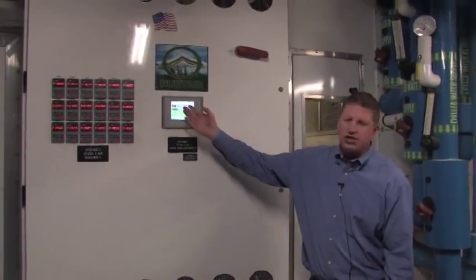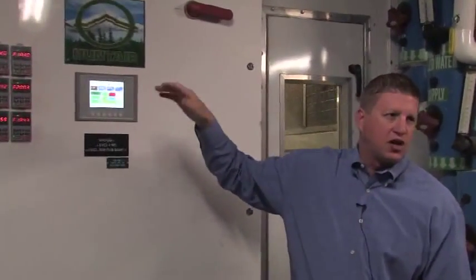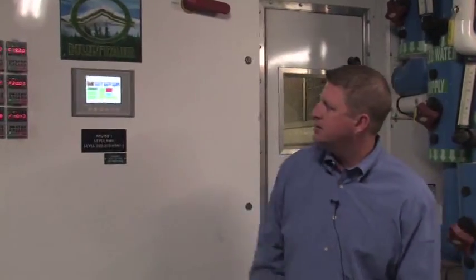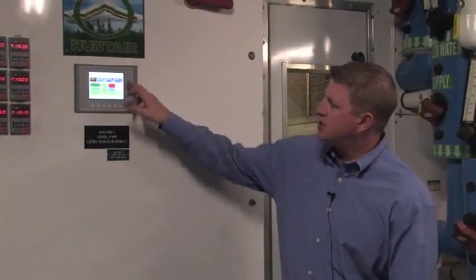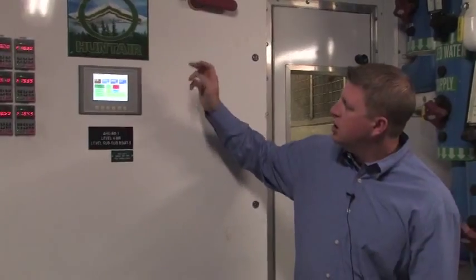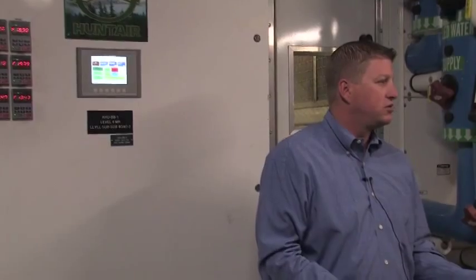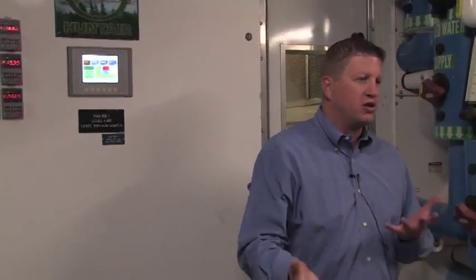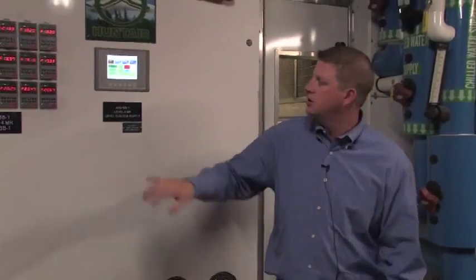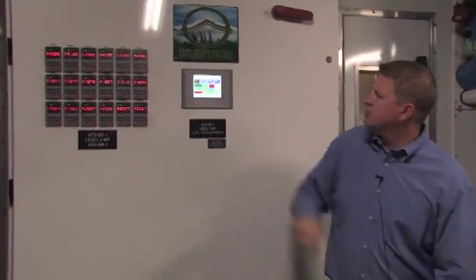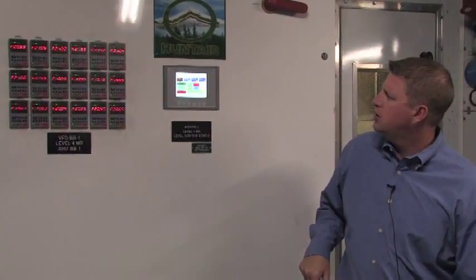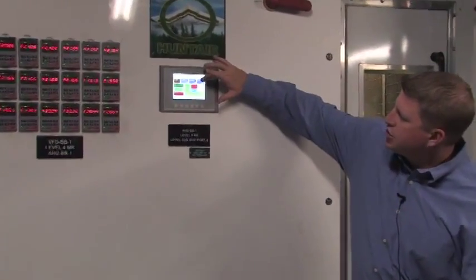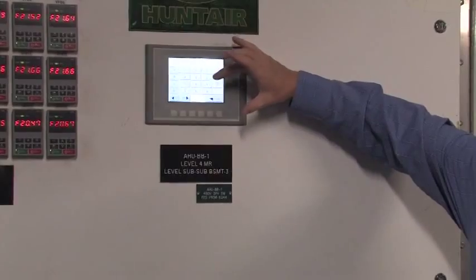All right. So now you can see it's locked in right around 20,000. It's going to fluctuate a little bit, but it's pretty low. So that's right around 20 hertz. Let's say I feel more comfortable controlling in hertz rather than CFM, because you never really know what the CFM was, but you tend to always know what the hertz was. So I will disable CFM control, and now I can control by this. I'll put it up to 30 hertz.